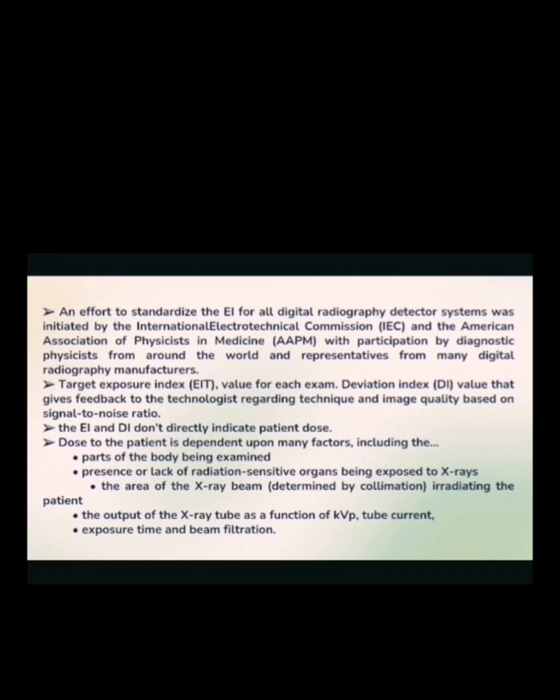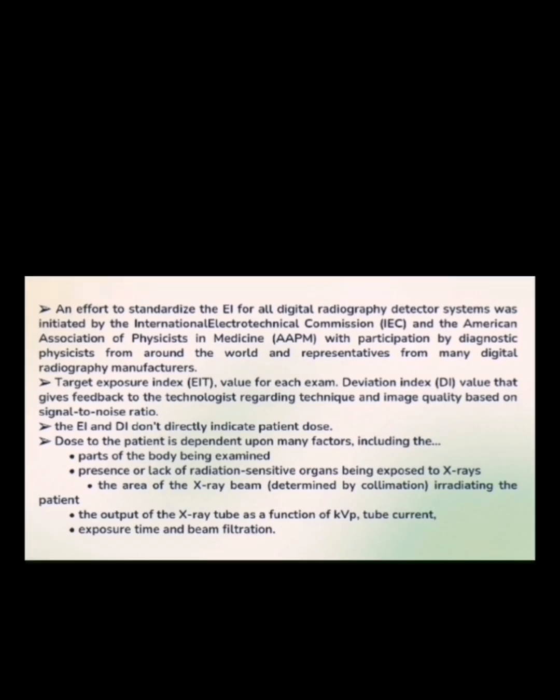And this requires users to input a target exposure index. So target exposure index is a value for each exam, and it indicates a deviation index. So deviation index again is the value that gives feedback to the technologists regarding technique and image quality based on signal to noise ratio.